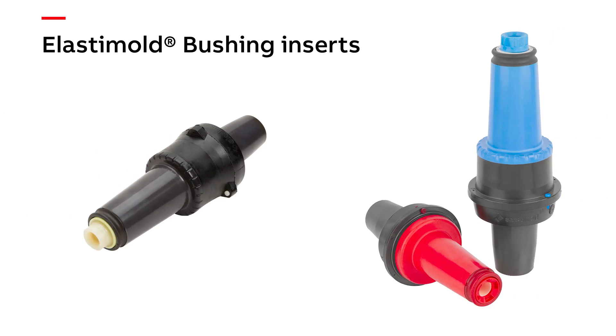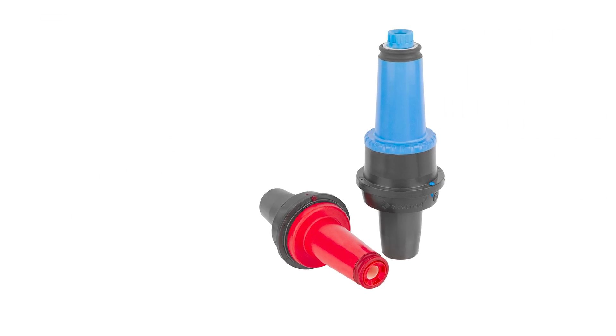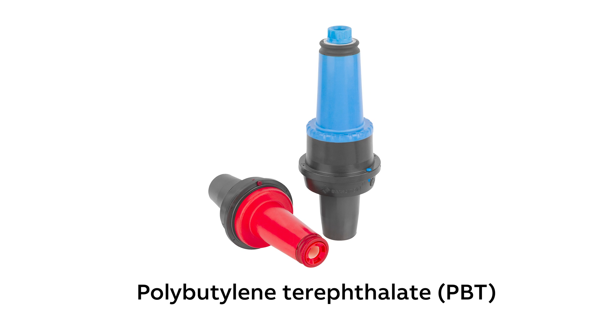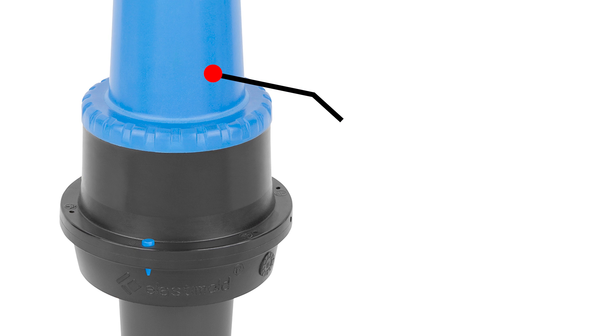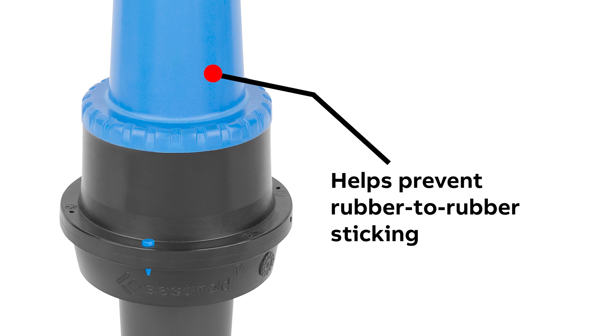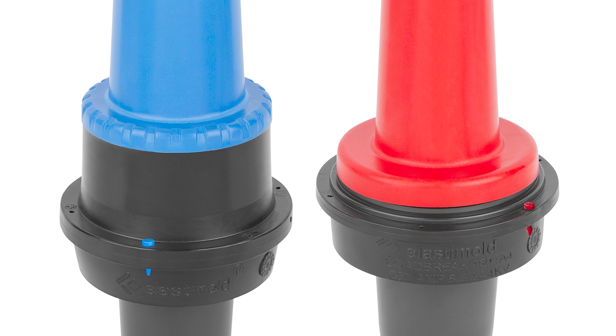If you're familiar with Elastimold cable accessories, you probably think of our elbows and bushing inserts. We're certainly known for those, but today I'd like to make you aware of some innovations that could really help you with the safety and reliability of underground distribution systems. Take the bushing insert — we have a PBT bushing insert line that is designed to prevent the rubber-to-rubber sticking that can make it very difficult to break the load and remove the elbow. With our PBT line, your crews won't have to struggle physically to remove the elbow or risk damage to the equipment.